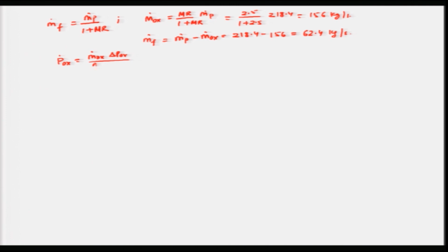As I told earlier, the power of the oxidizer is m dot oxidizer times delta P oxidizer, divided by the efficiency and rho of oxidizer. If I substitute those values, that is 156 into 5.5 into 10 power 3 divided by 0.9 into the density 1150, I will get 829 kilowatt. This is a very big number, around 0.829 megawatt.